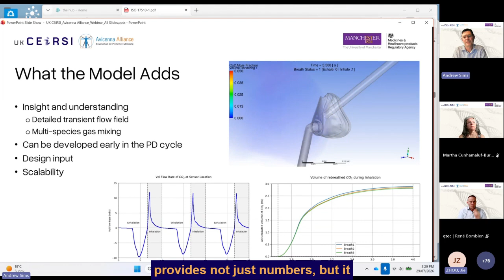Looking at the results, we can see the concentration of carbon dioxide, which is shown in the animation that's on loop play at the moment. During exhalation, you can see the carbon dioxide rich air coming down the tube, and then that is delivered into the plenum of the mask where it is mixed, and we can see that some of that is vented out into the atmosphere and removed from the system that the patient will breathe. So we can just visually see that we're removing carbon dioxide.